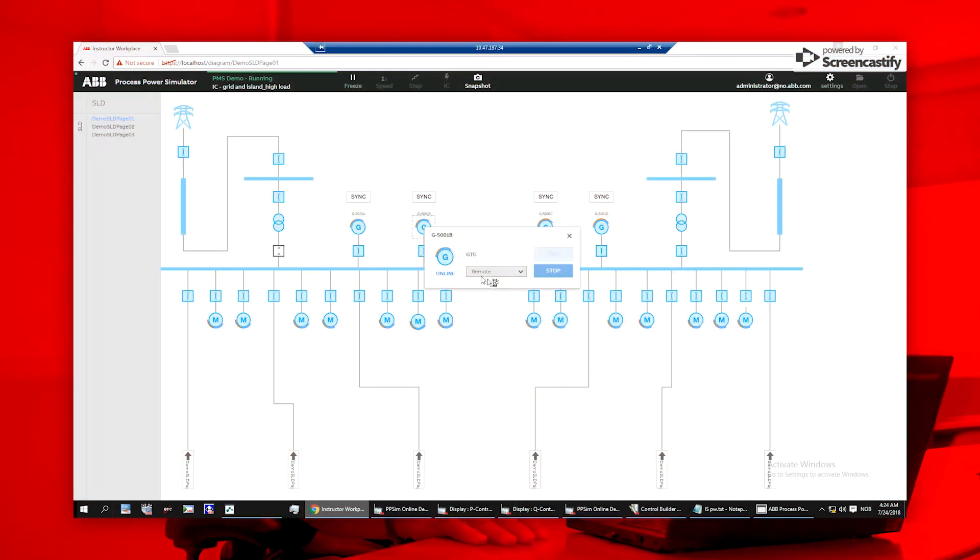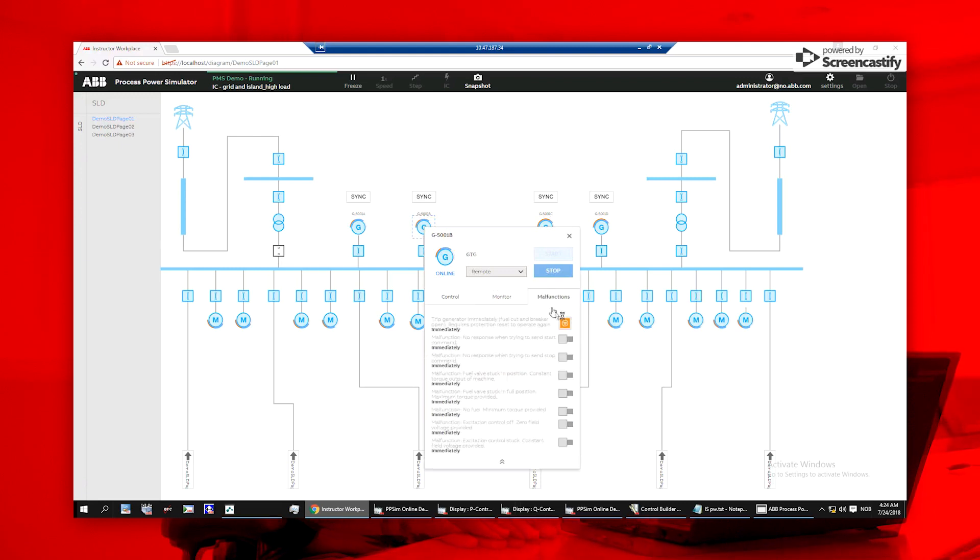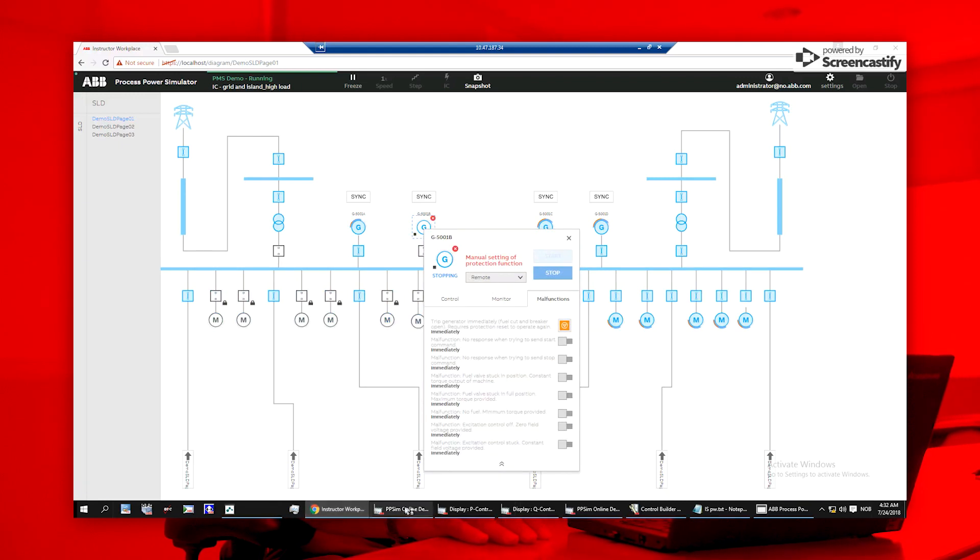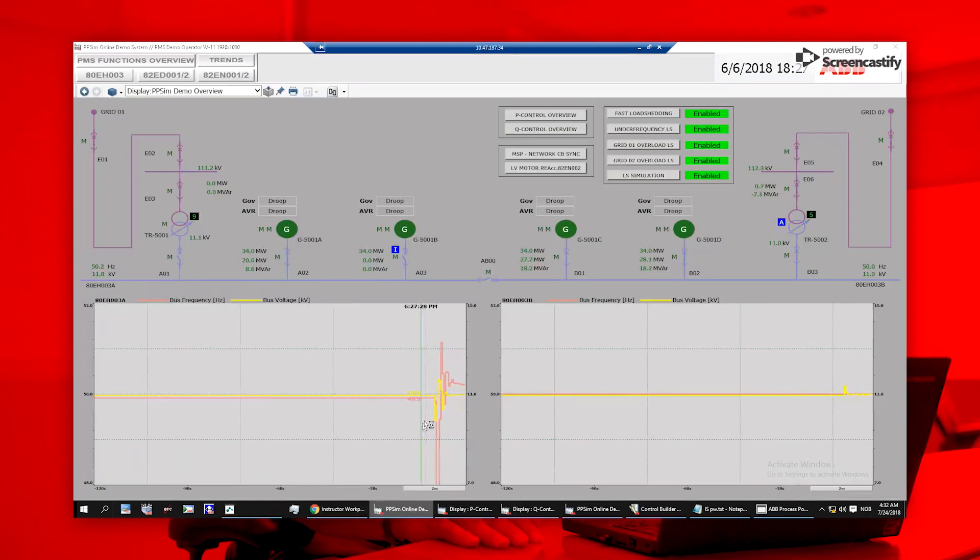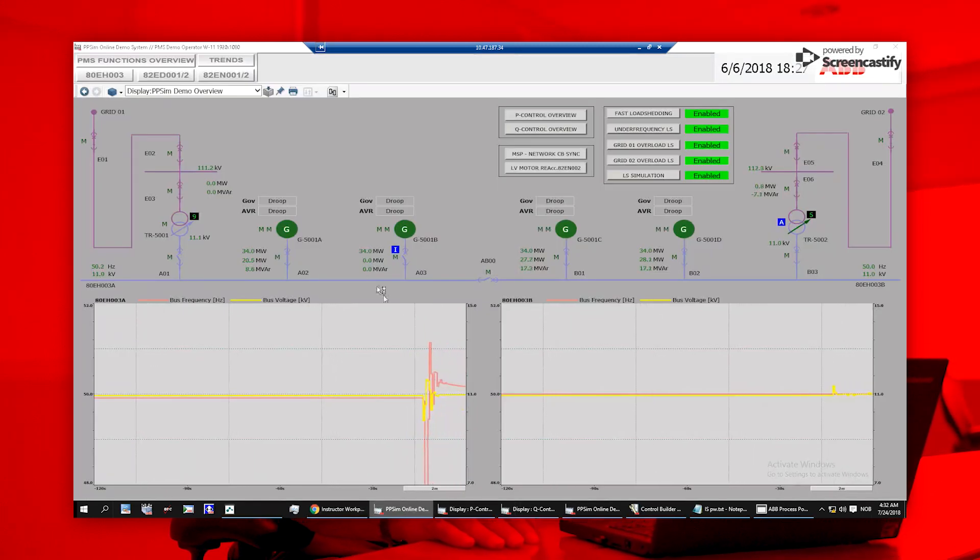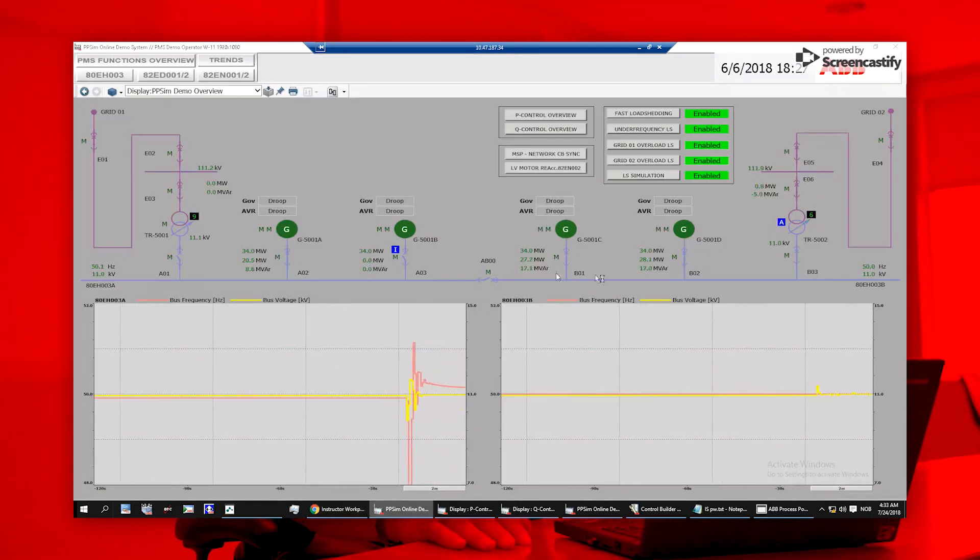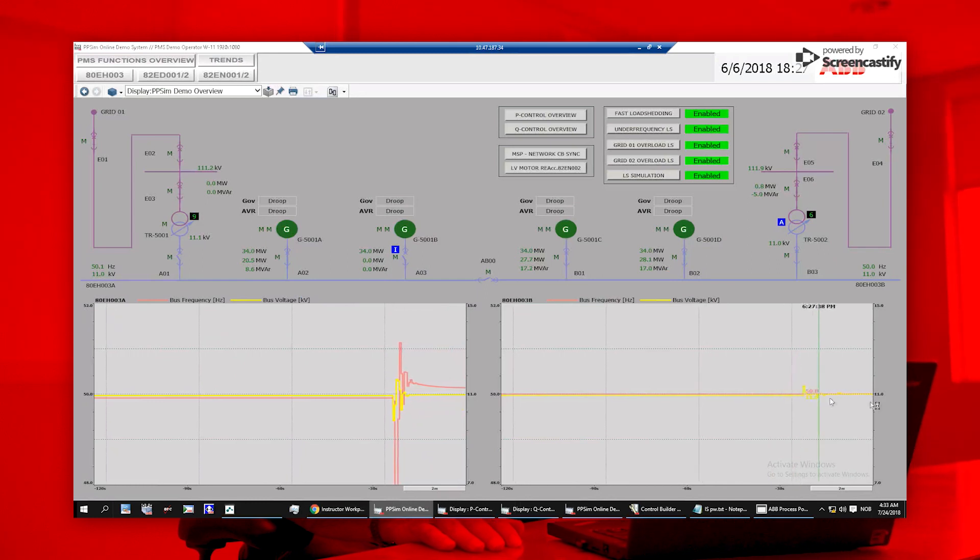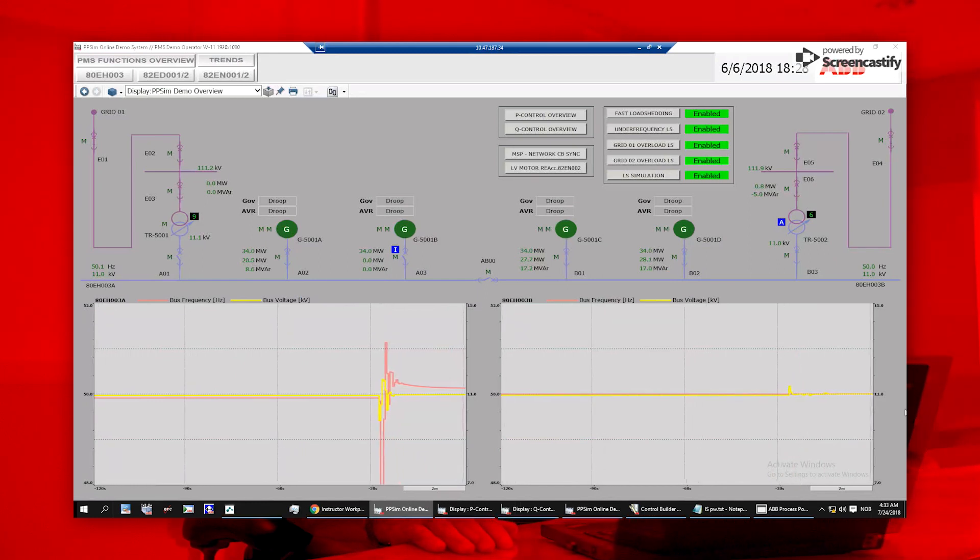Instructors can also trigger or pre-define malfunctions, such as generator trips. Once a generator is tripped, users can view the ABB Ability System 800XA workplace to test and verify control system actions. In this example, a load shedding action occurred as intended.